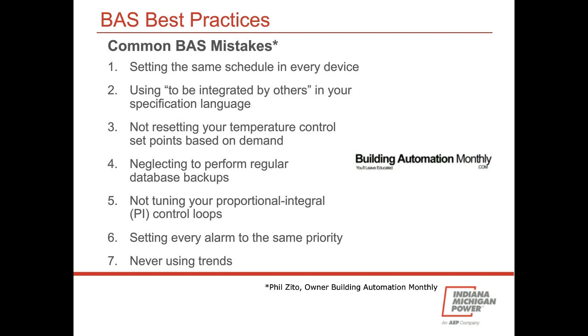All right, not tuning your proportional integral control loops. The problem is, over time, dampers get sticky, coils get a little gooey, and things just don't react as fast as they used to. That can lead to a hunting condition, with the control loops reacting too fast and overshooting the set point, et cetera.